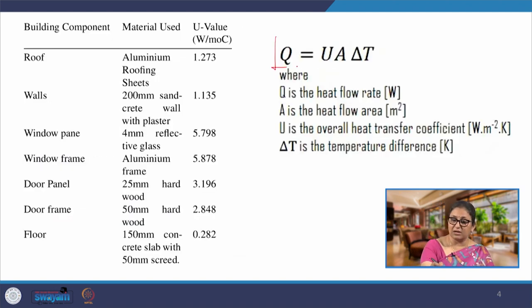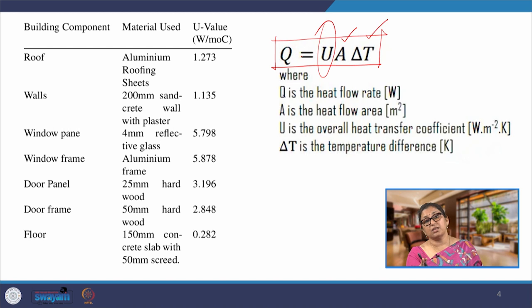So what we have is we have this clear formula: Q is equal to UA delta T, again for the walling materials or the roofing materials. What will remain the same if we are comparing only between the choice of materials, not going into design for these calculations? The areas will remain the same, the delta T will remain the same, the difference of indoor and outdoor temperature will remain the same. What is changing is U, and we have already seen that how important is this U value. We reduce U value by half, the energy consumption or the heat exchange reduces by half. We double it, the Q doubles up. So it is directly proportional.